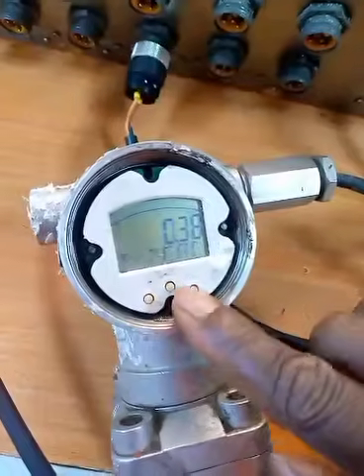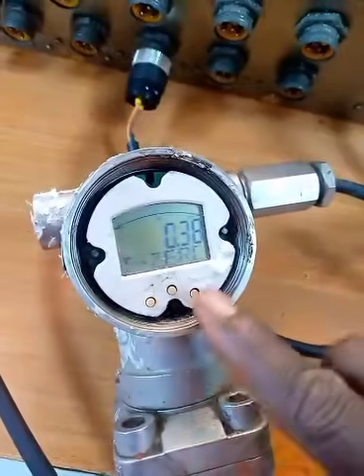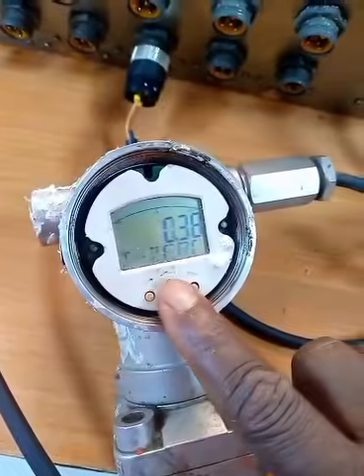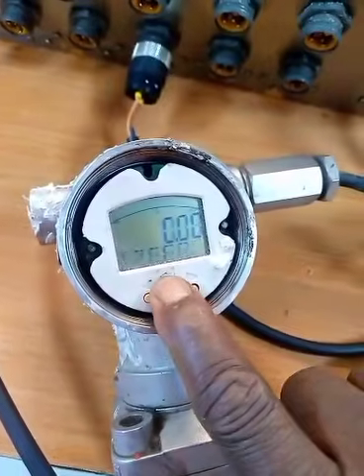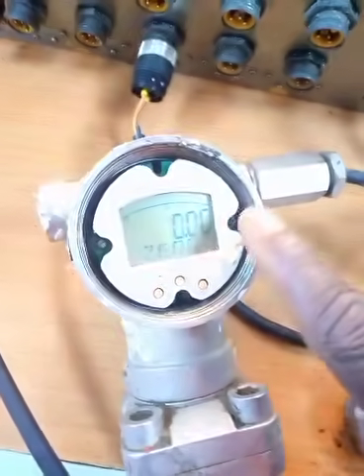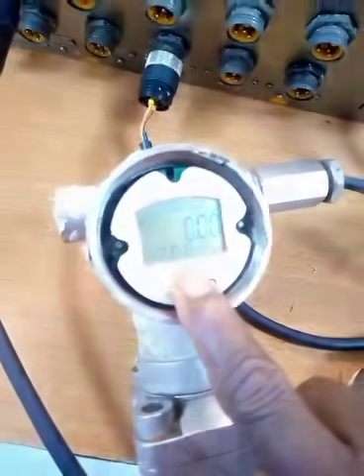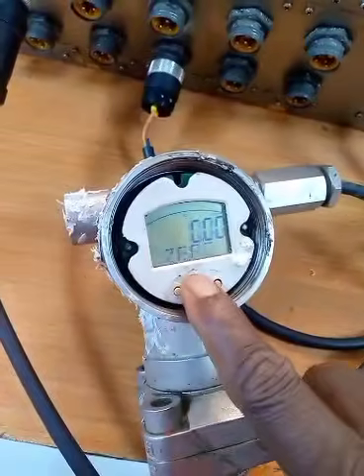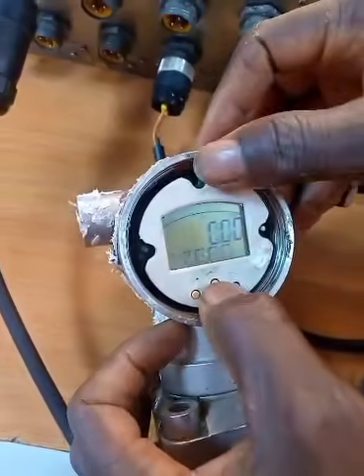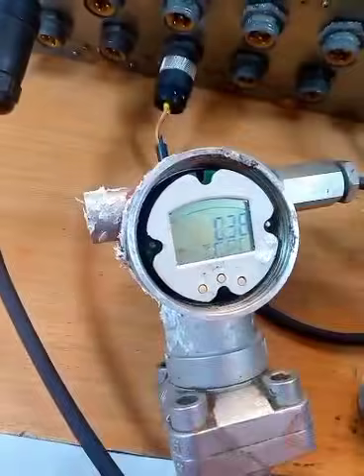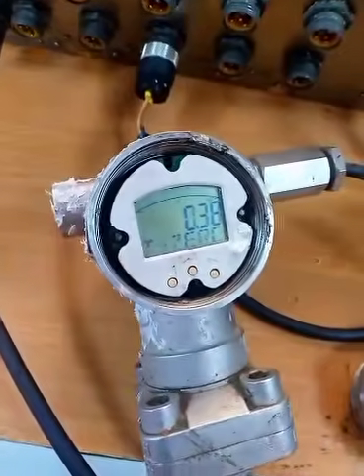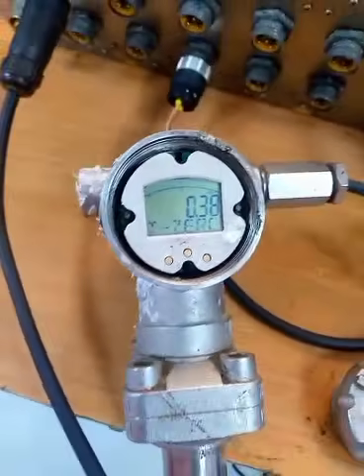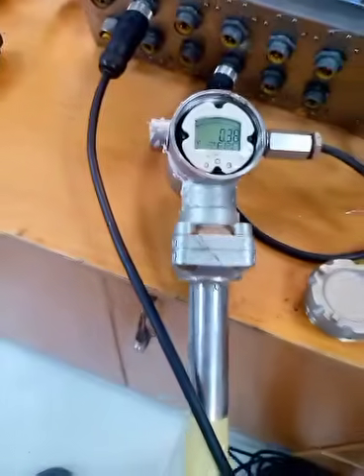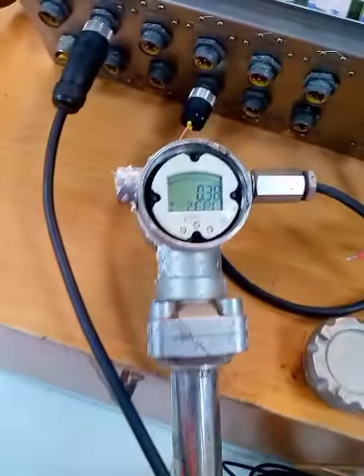So you come here and you see one central button — not the one on the left and right, the center one. You press it, and it shows 0.0, then you press it again. Once you press it again, it has acknowledged it. You press it about two times, and with that you have 4 milliamps on the screen.